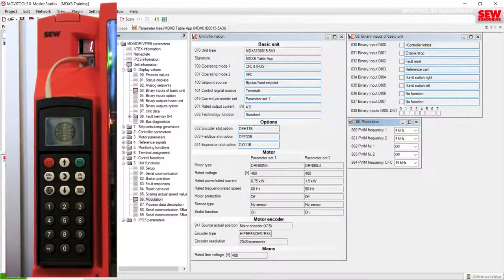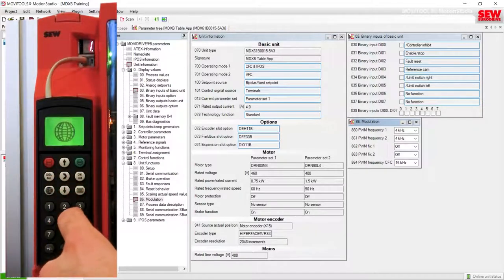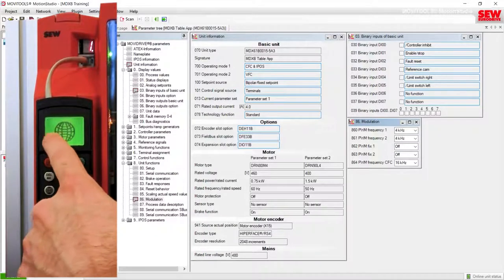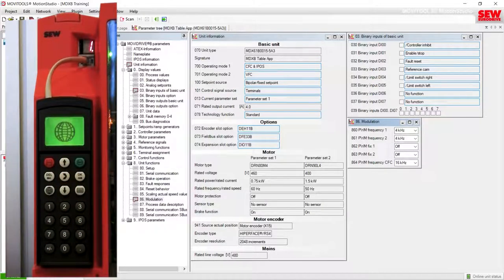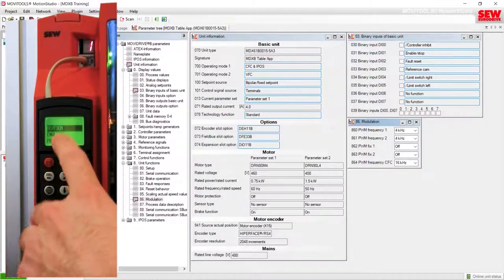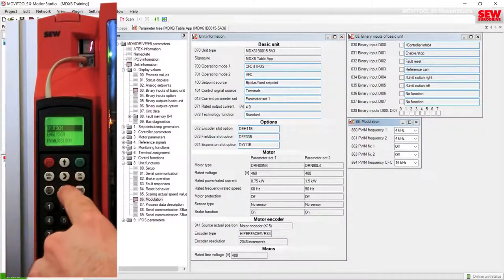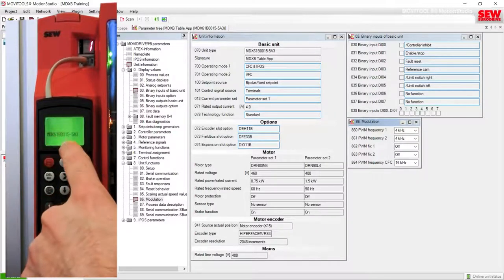Now we're looking at the keypad and currently the backlight is not on, so to activate it we just press any key. The backlight is now on, but currently we can't do anything with the keypad because there is a globe icon on it. This globe icon appears because this keypad has been set to its factory condition — you will only see this if you are using a new keypad or if you reset the keypad using one of the menu items. So we press the globe icon, which pulls up the available languages. We select English using the down arrow, then press the right arrow to confirm. The keypad now reboots with the English language.